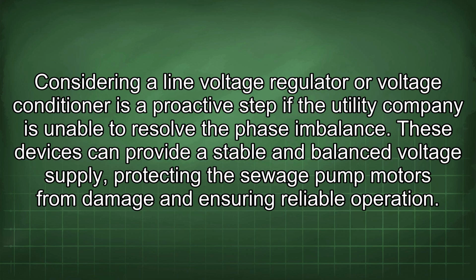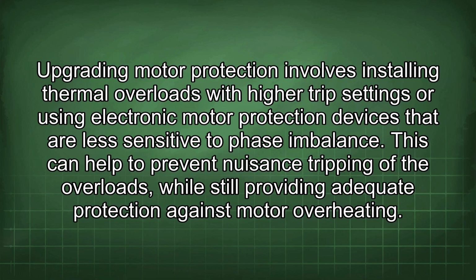Upgrading motor protection involves installing thermal overloads with higher trip settings or using electronic motor protection devices that are less sensitive to phase imbalance. This can help to prevent nuisance tripping of the overloads while still providing adequate protection against motor overheating.